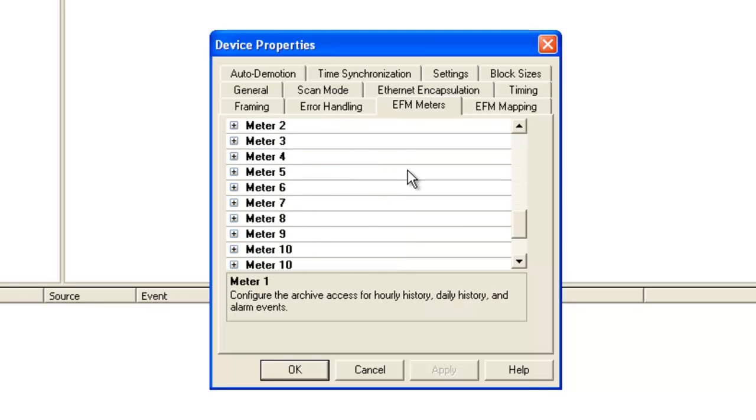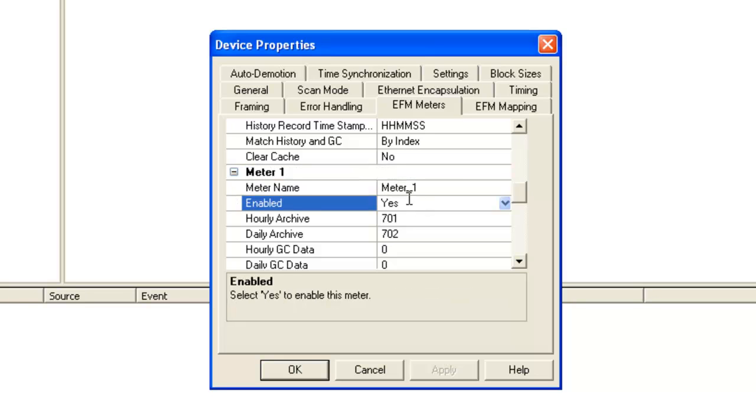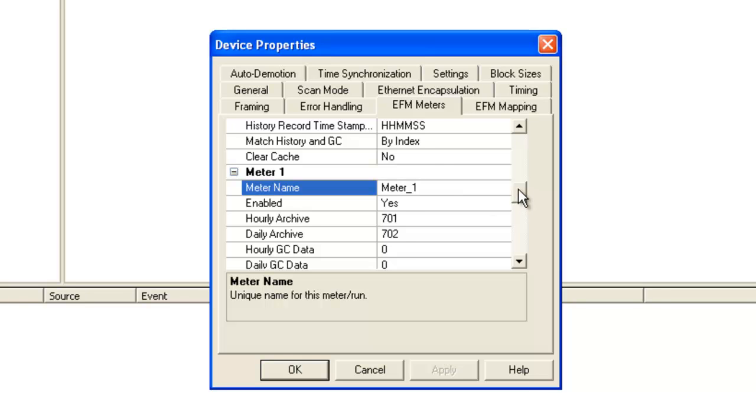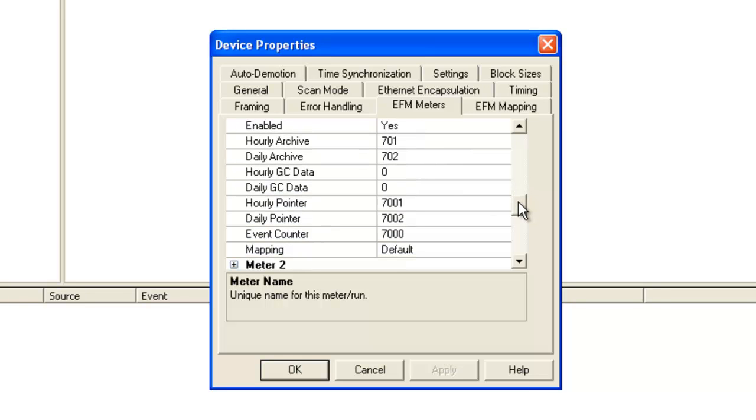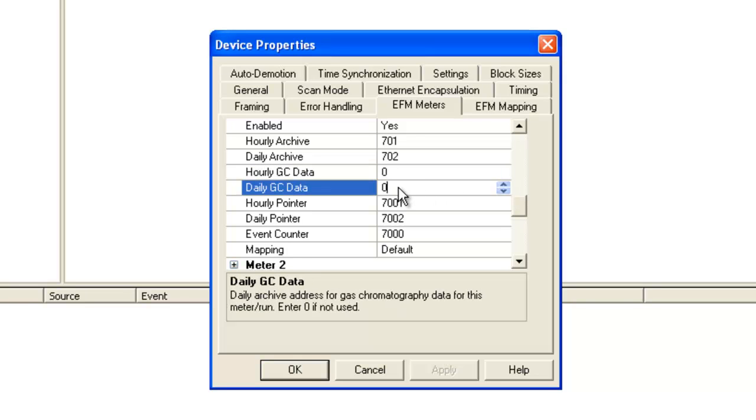Enron Modbus supports up to 12 meters. Meter 1 is the only one enabled by default. Now each meter gets a unique meter name, which we use internally as an alias in the server. We have support for both hourly and daily data, and gas chromatograph data. With these configured to zero, it means we're not interested in GC data at the moment.